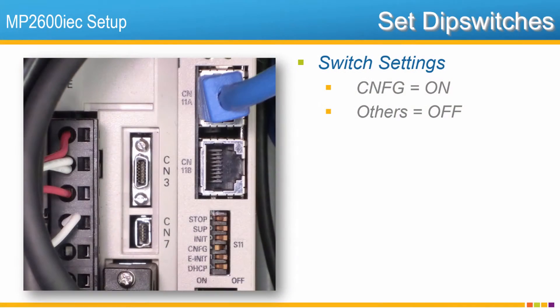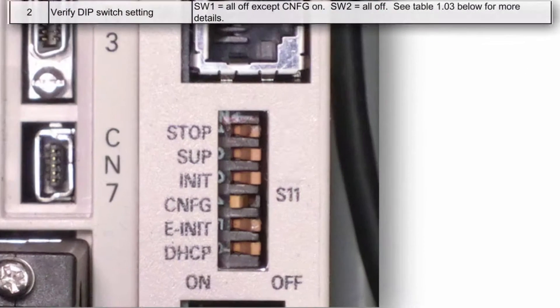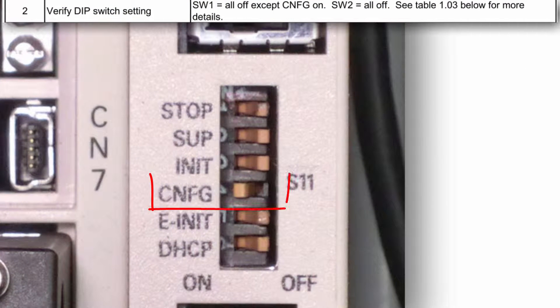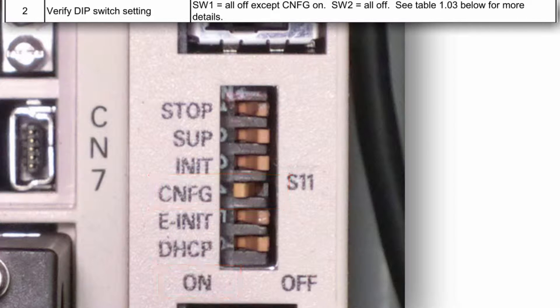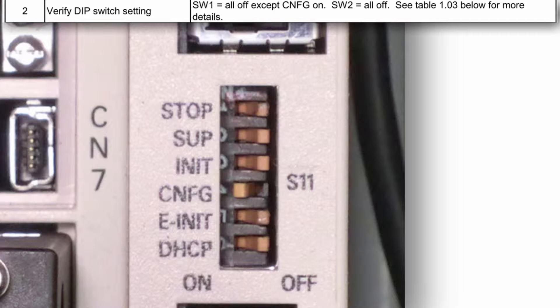Next, check the DIP switches. Only the config switch is normally set on. All the others are normally set to off. Config on at power-up allows the controller to configure the servo pack and internal IO. Leaving it on does not affect the operation of the controller.